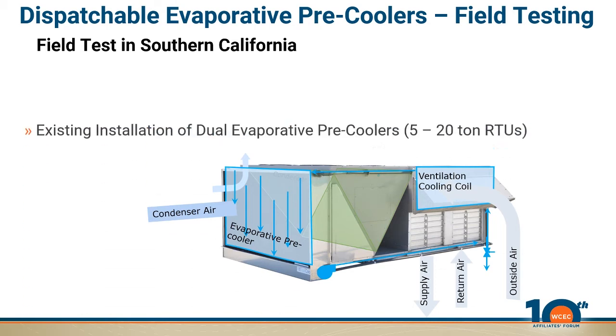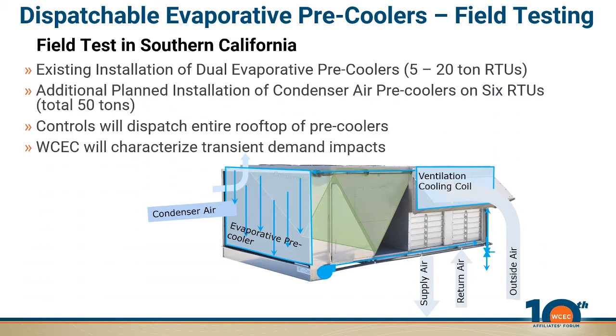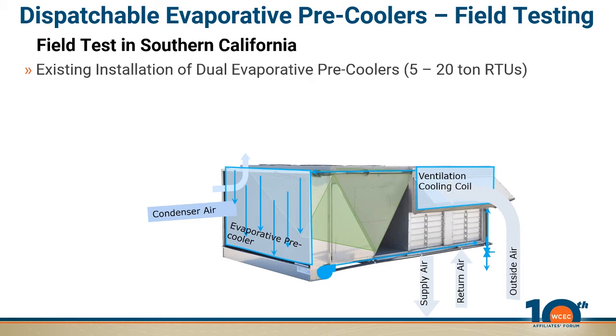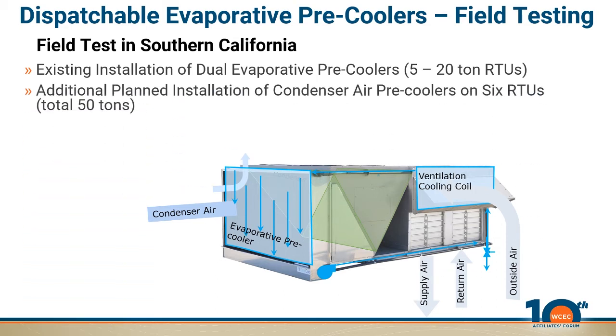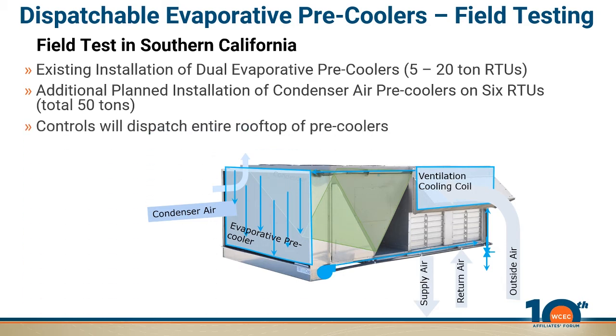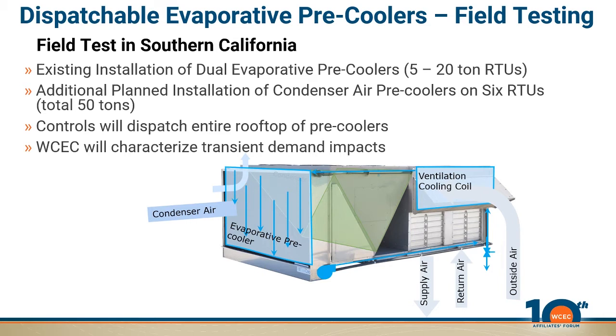For the field test, we're going to go to an existing installation. This is a dual-cool unit — an evaporative pre-cooler, like we've discussed, that also cools the ventilation air indirectly by pumping the sump water. There's an existing installation of these on units of 5 to 20 tons in Southern California. We'll also work with a planned installation of additional condenser air pre-coolers on 6 RTUs. We'll control and dispatch the entire rooftop of pre-coolers and measure exactly what happens — essentially reproducing what we did in the lab, but on a real building in the field, because everybody cares where the rubber meets the road, which is an actual building.